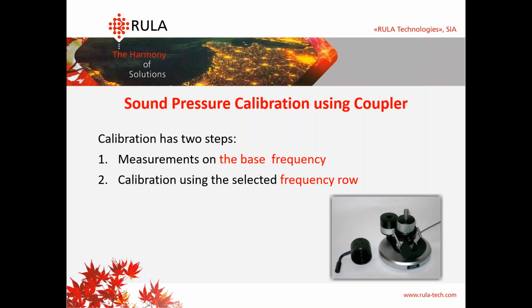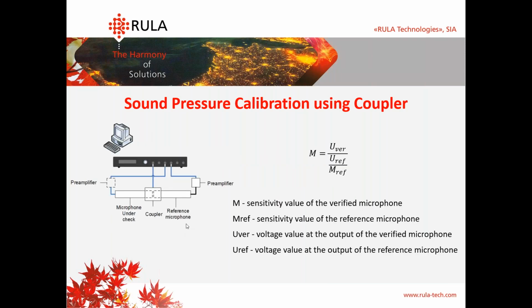So here, let's discuss the sound pressure calibration steps using the coupler. You can see it on the screen here. In our first step, we make measurements with two microphones, the reference and the microphone under check, on their base frequency. After that, we go through the desired frequency row and generate sine waves and get the data. And after that, we calculate the FRF, find the nonlinearity, and create a report. Here you can see the main connection scheme. We have our controller, two microphones inserted in the coupler, and maybe you can have a preamplifier for your microphones.